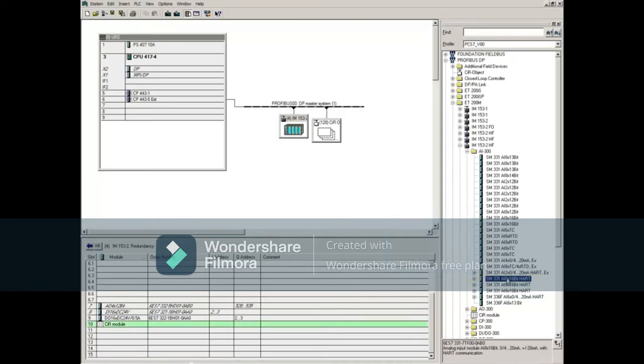Expand the AI300 list and select the desired HART module. For this example, we'll pick SM331 AI 8X16bit HART. Drag and drop it onto the CIR module entry on the left.